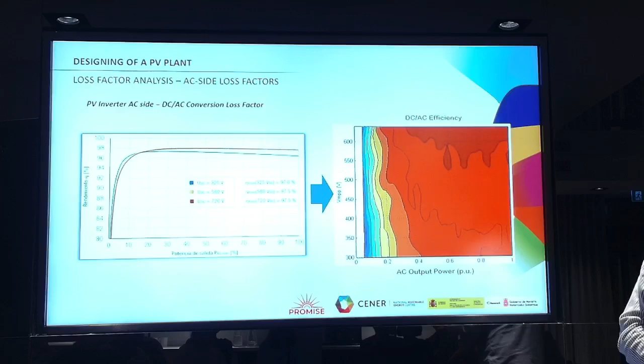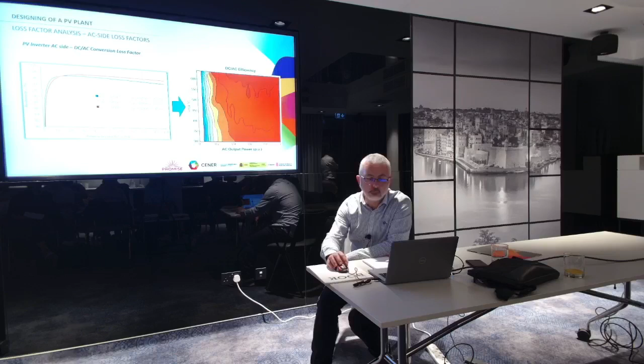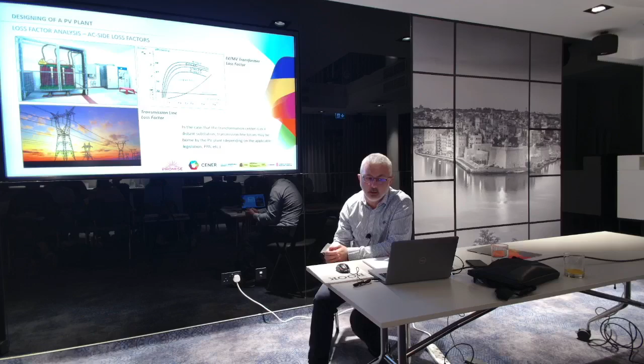The AC side loss factors involve, obviously, the PV inverter too. So the conversion from DC to AC is not perfect, obviously, and this is an efficiency that depends on the level of the output power. It depends on the voltage. It's very usual to see this type of curves, the maps of efficiency. And in the AC side, we're taking into account the losses of the low voltage and medium voltage transformer and the transmission line. In case the transformation center is at a distance from the substation, the transmission line losses could be very important.